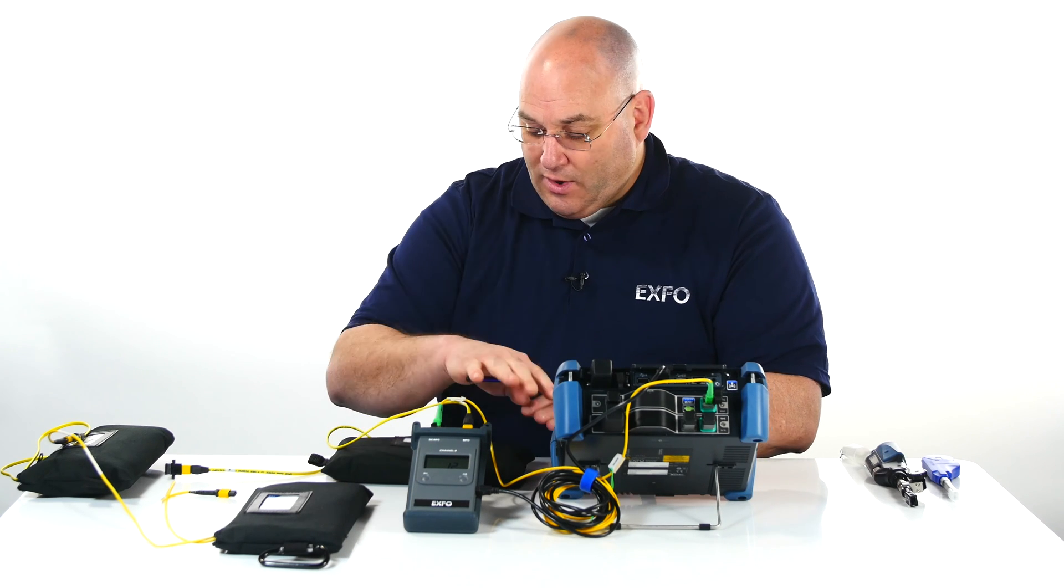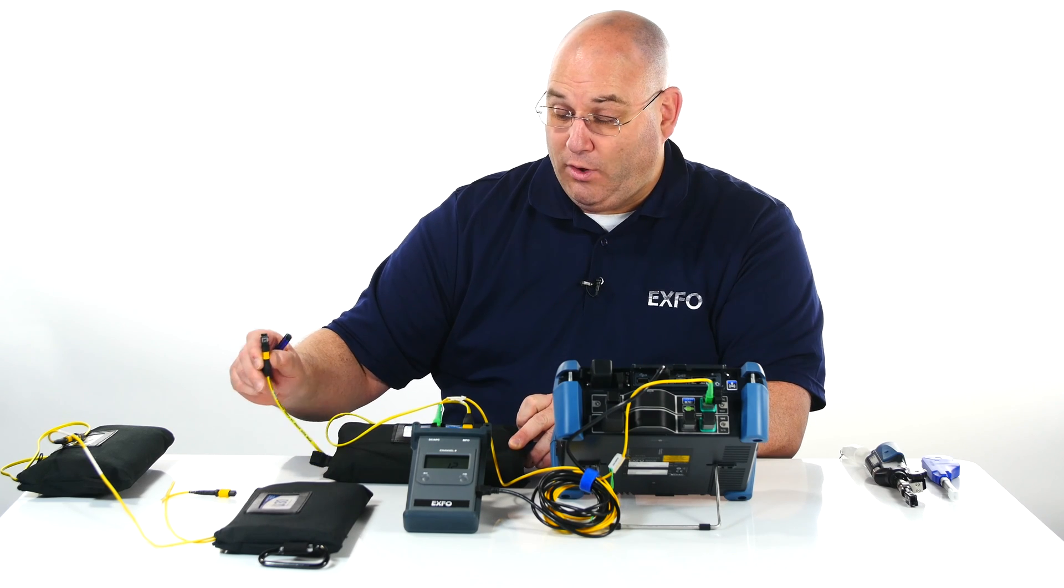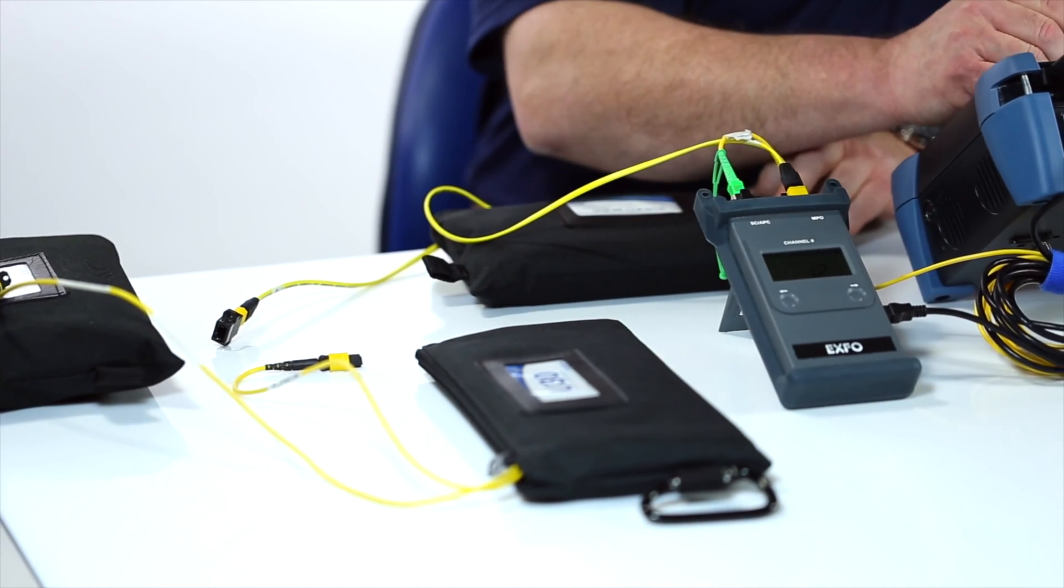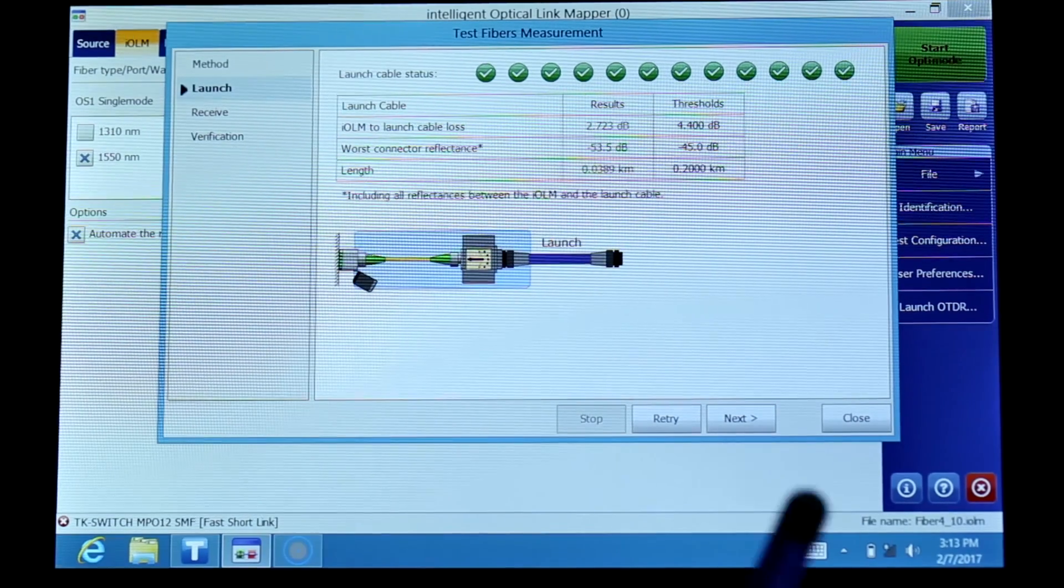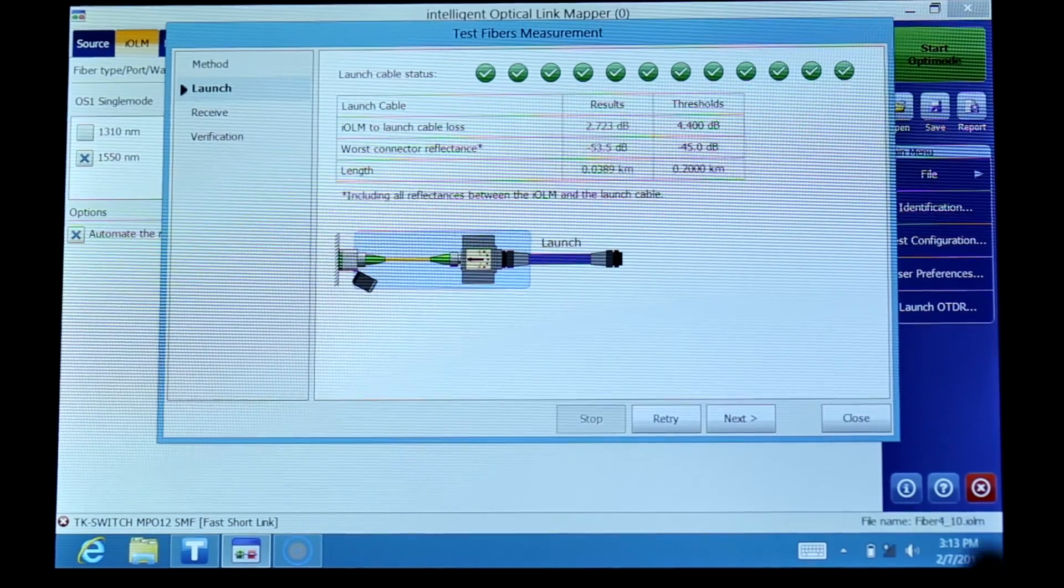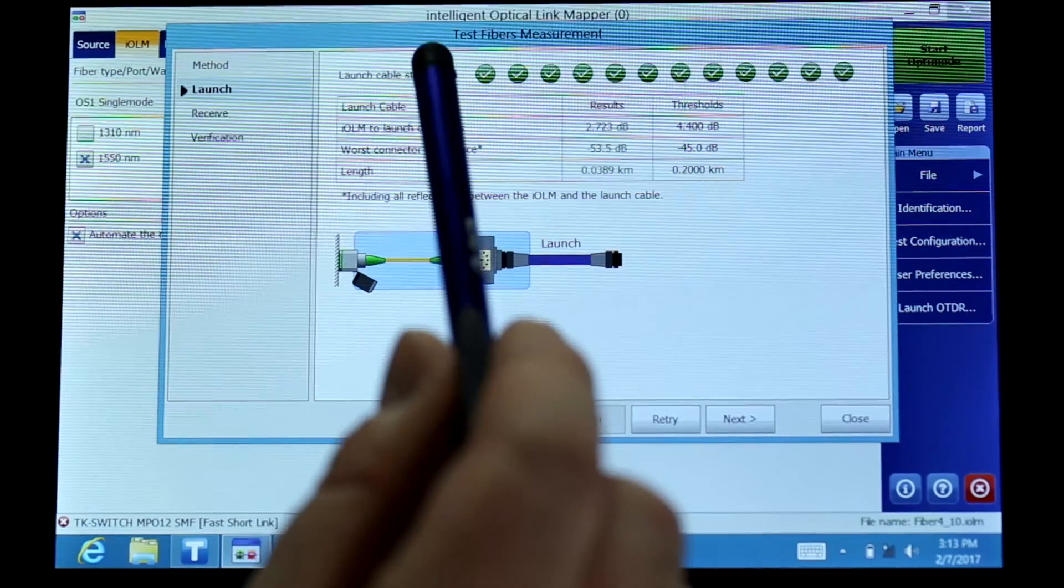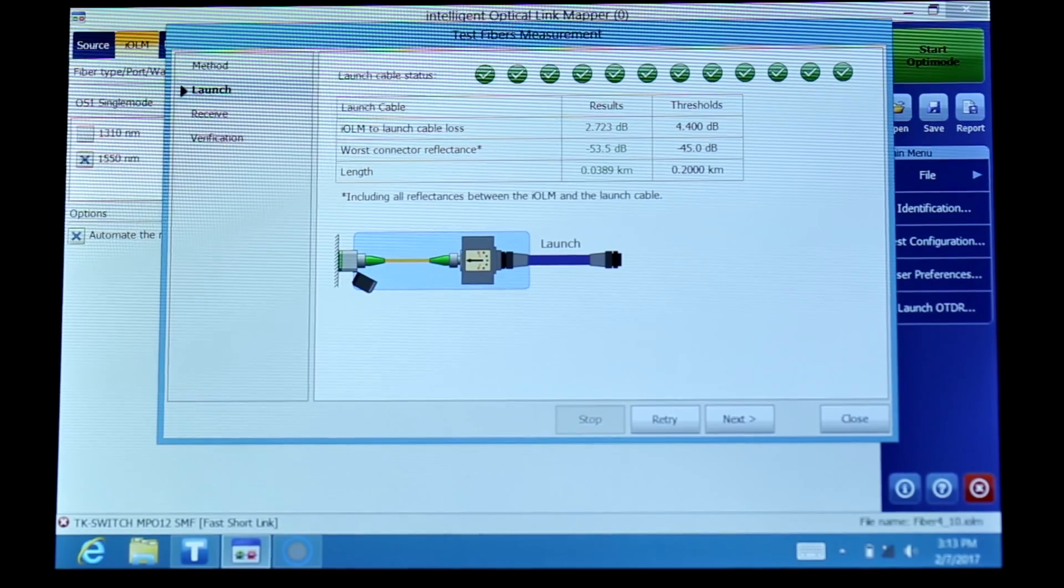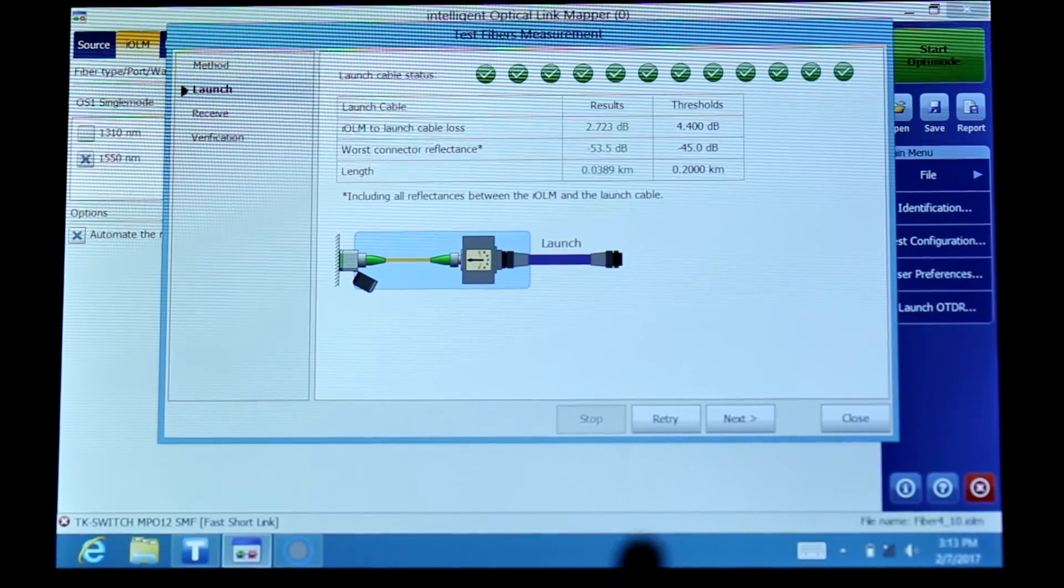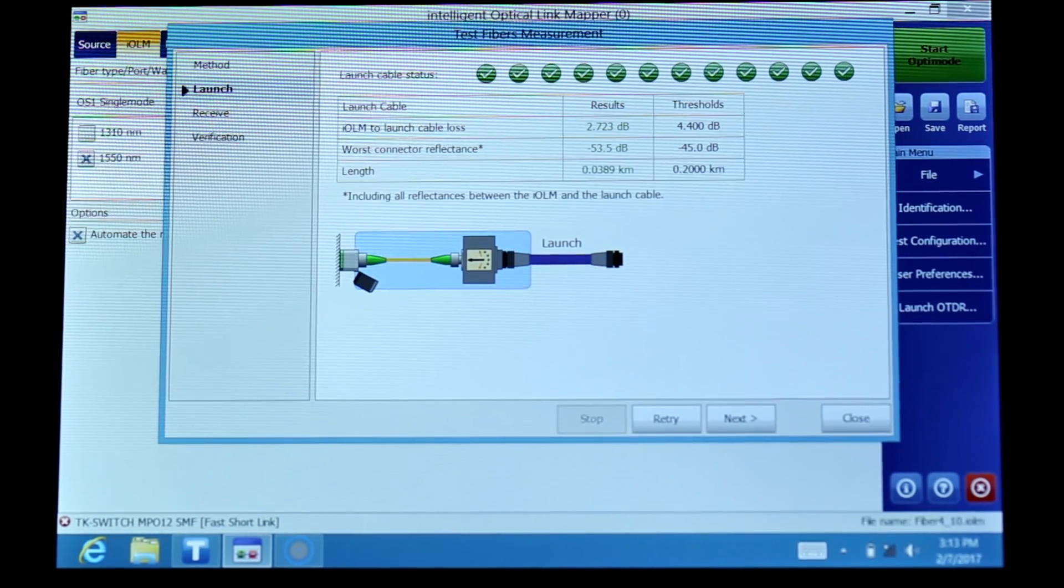So when you have this connection and the other end of the launch cable remains open, you can press measure and we'll come back to show the final result. What we see now is that the launch cable only connected has been validated in the calibration. We see the 12 round green checks indicating that the calibration has been okay in terms of measuring the length and the continuity.